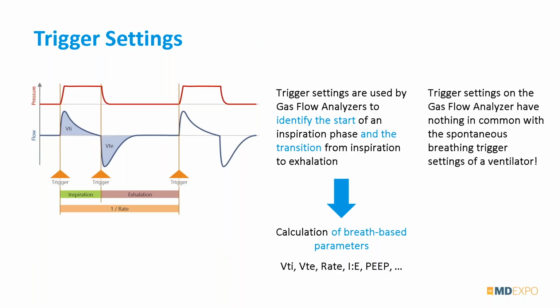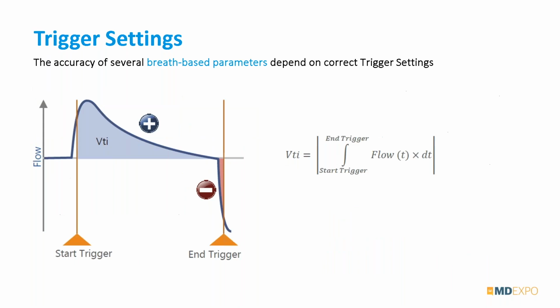So how do we do that? We have settings in our gas flow analyzers where we have to tell the device when it should trigger. If we don't have these settings correct, then either we have no measurements of these parameters, or they can be significantly off. If the timing of my triggers is not close enough to reality, then that can lead to calculation errors. For example, here we see a typical flow waveform during an inspiration, and my gas flow analyzer needs a start and an end to see for what time it has to calculate my flow and mathematically integrate it and say, okay, this is my volume.